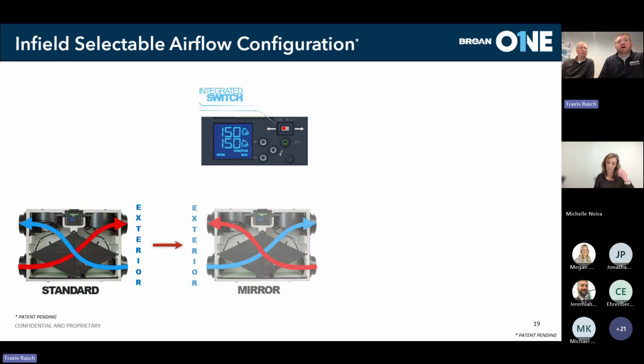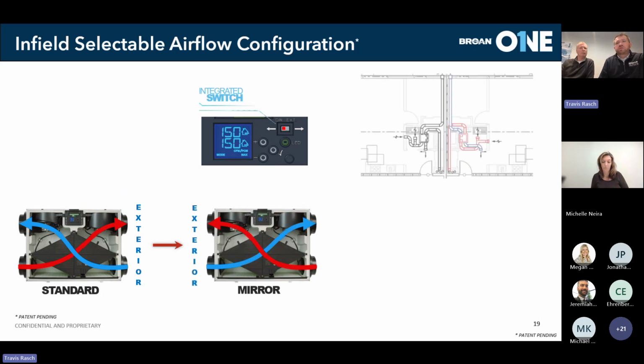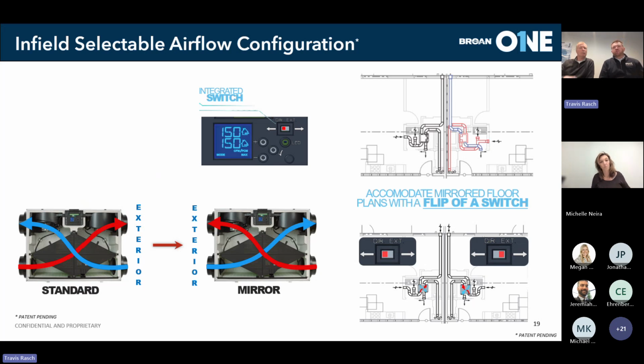Something that's unique to this platform in the industry, and that really helps in those multifamily designs where we've taken a floor plan and simply mirrored it, whether across a shared wall assembly or across the corridor, is what we call in-field selectable airflow configuration. If we've got a design like you see in the upper right corner, in the floor plan on the left everything's great, the ductwork looks nice and clean, we found a good spot for this ERV to be placed. We then try to take that same location and translate it into the floor plan on the upper right. As you can see, that ductwork gets more complicated and leaves opportunity for, I'll say, creative freedom out in the field. If the ductwork isn't clean, they might route it differently than you've planned.